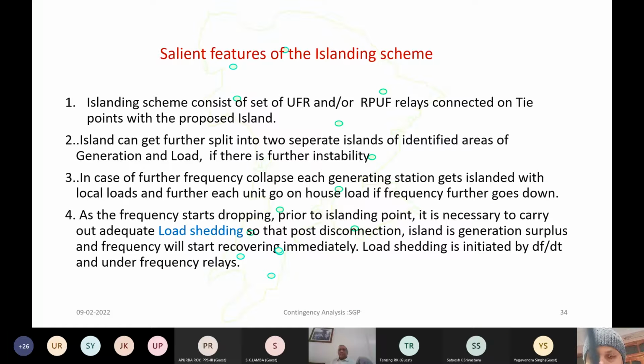One of the special protection schemes is also the islanding, or controlled isolation, scheme. So we'll see what an islanding scheme basically constitutes. The islanding scheme consists of a set of under frequency relays and reverse power under frequency relays connected at tie points with the proposed island. So the first step of the islanding scheme is basically to propose an island. So you say Delhi is an island to be created. Once you decide the proposed island, then you identify how many points the proposed island is interconnected with the grid.